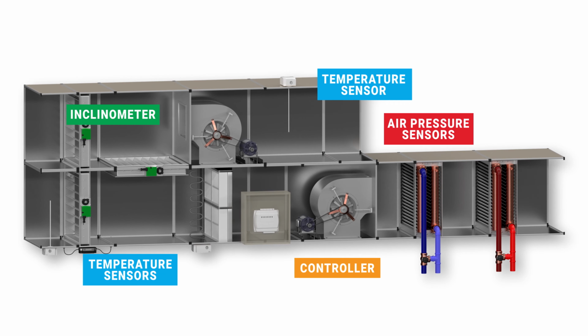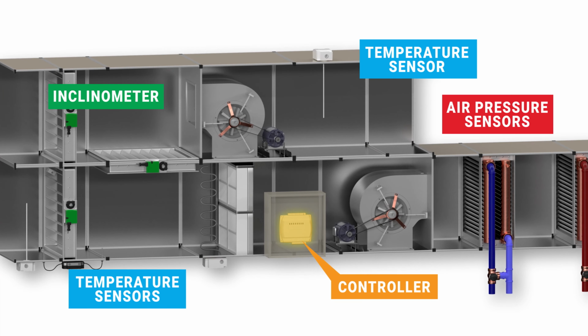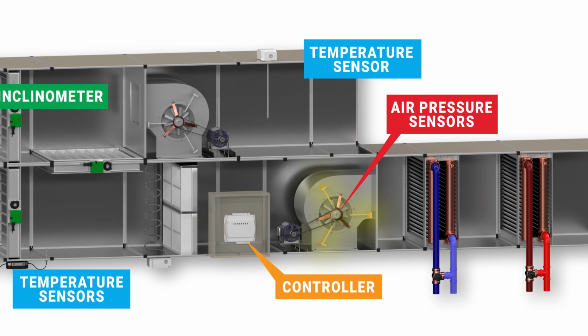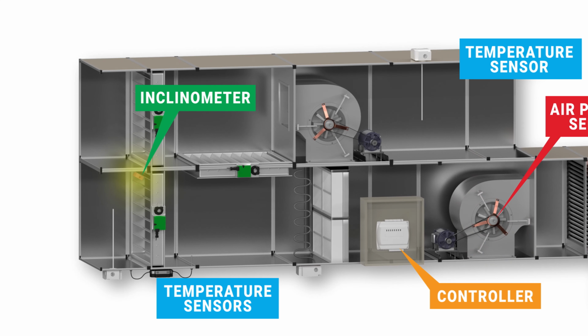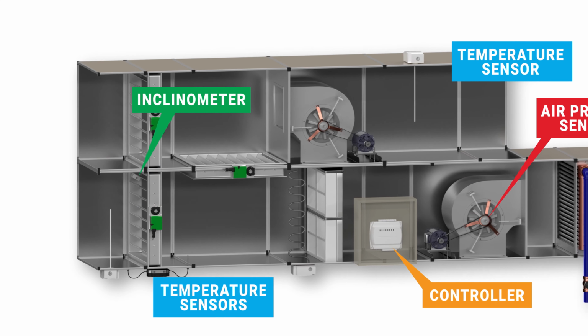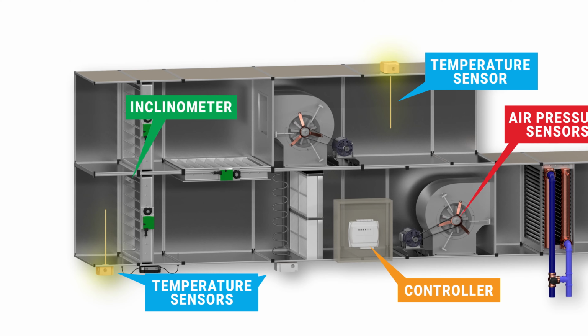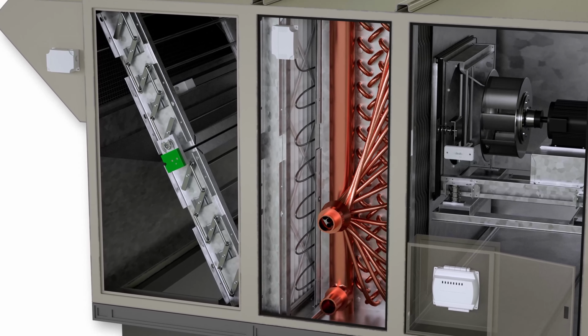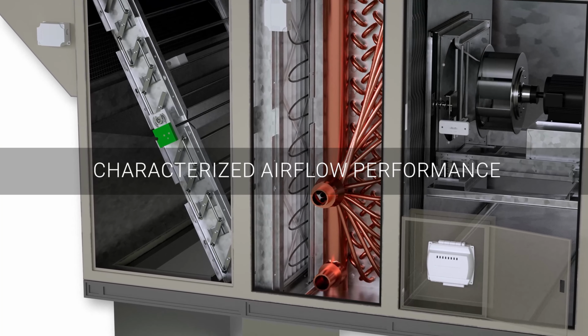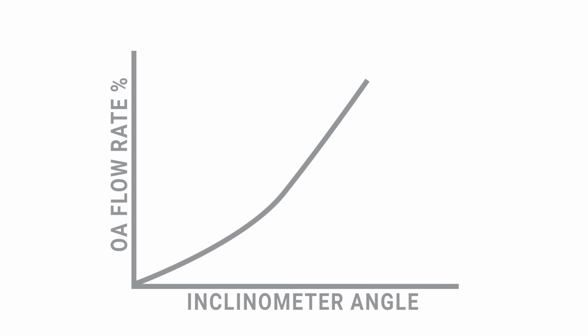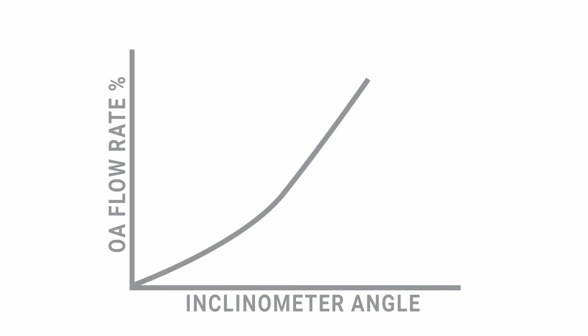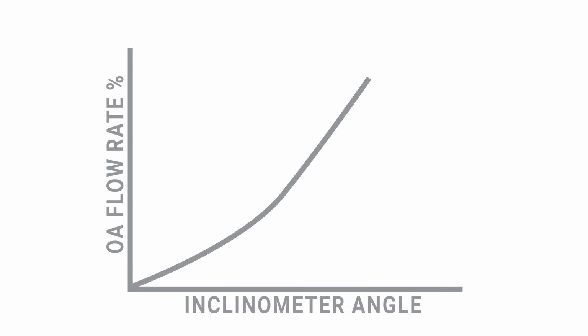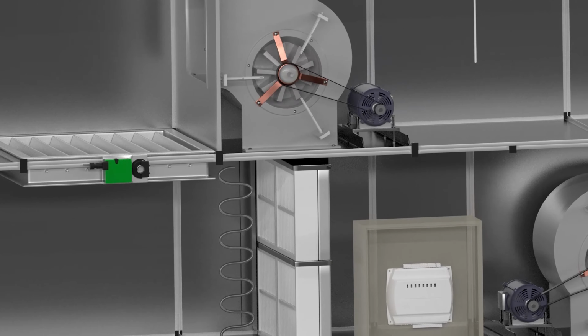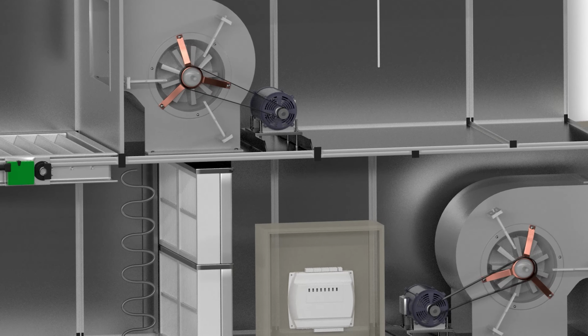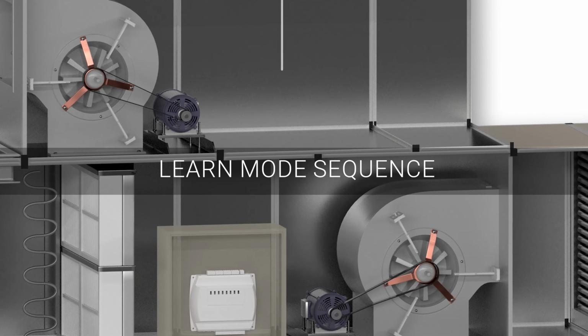The airflow measurement system consists of the following components: the AFMS device, a supply air measurement, an inclinometer mounted on the damper blade, and temperature sensors for outside, return, and mixed air. The system measures outside and return airflow by characterized airflow performance. Characterized airflow performance uses an airflow characterization curve, similar to a pump curve, to measure the supply, outside, and return airflows moving through the equipment. The characterization curve may be automatically generated by the integrated Learn Mode sequence.